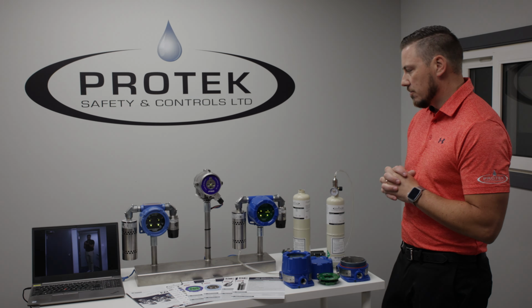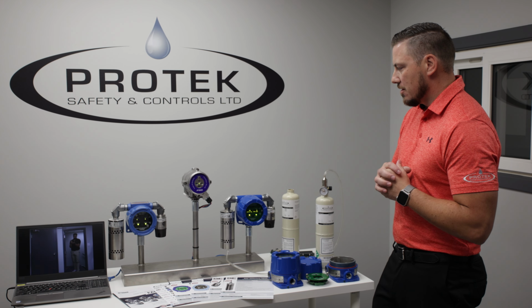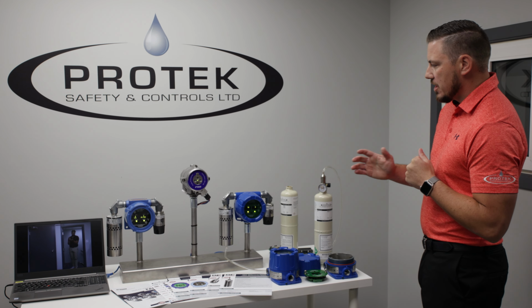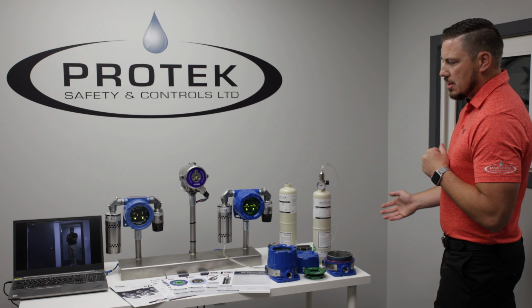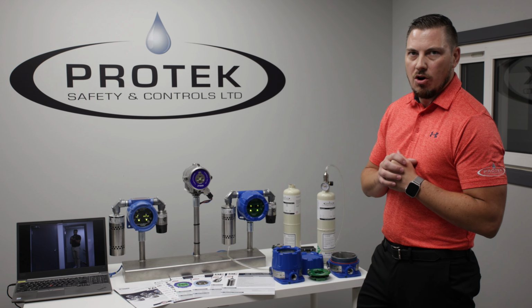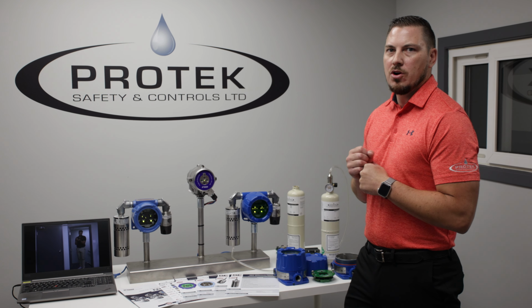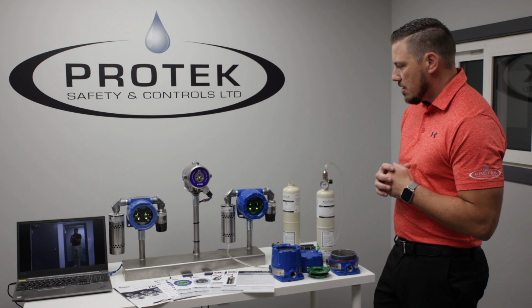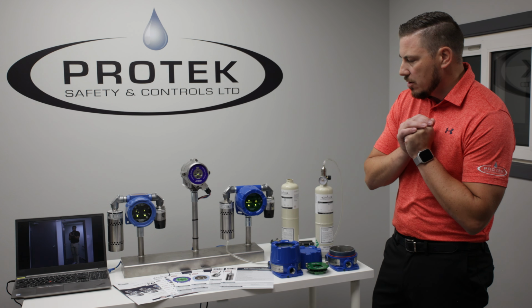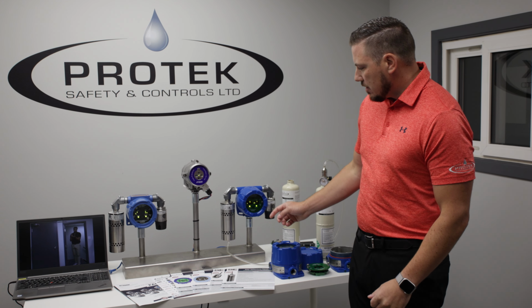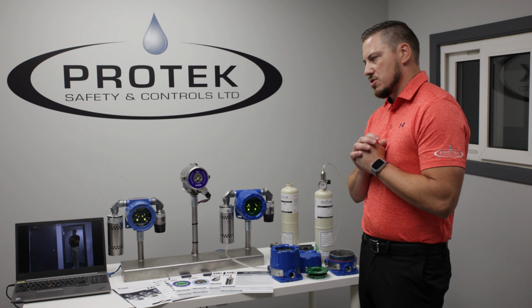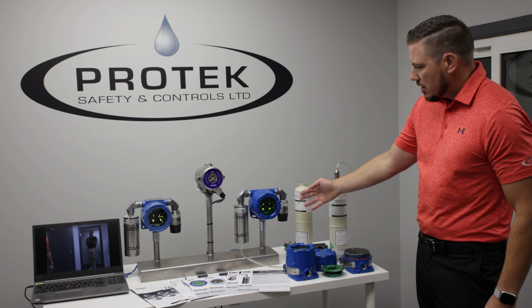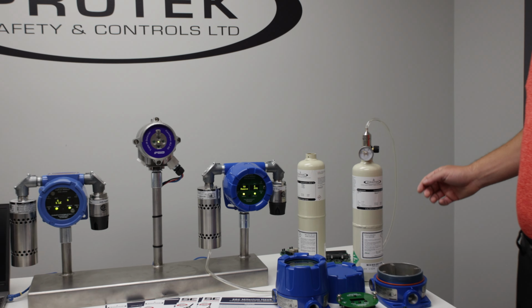We're just waiting for the sensor to finish the calibration, applying that known concentration long enough to ensure that all that air is purged out of that sensor. In any moment now it's going to tell us calibration complete, remove cal gas, and then the status is actually going to change. As you can see, it now scrolls across the screen, remove calibration gas.